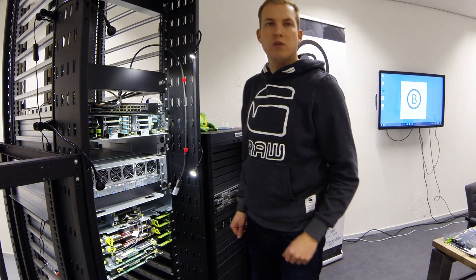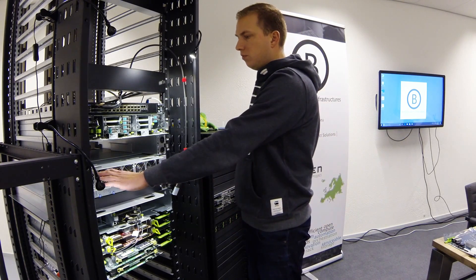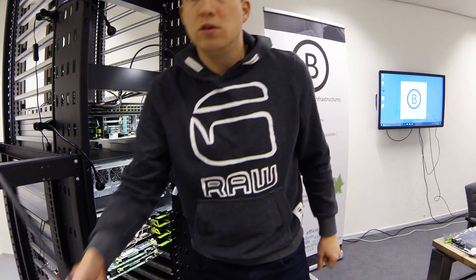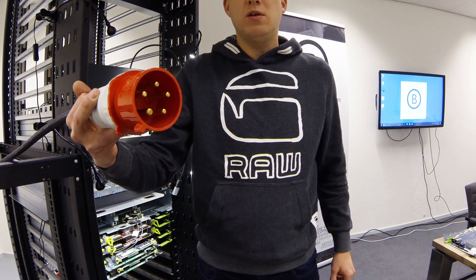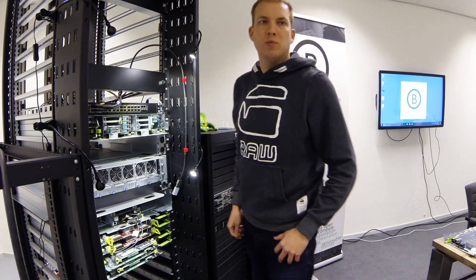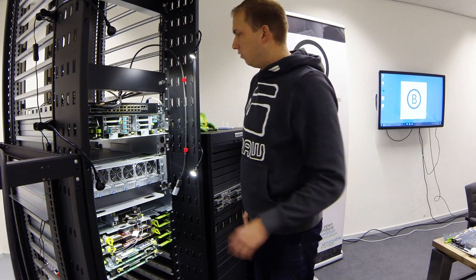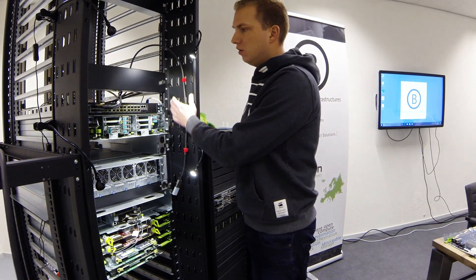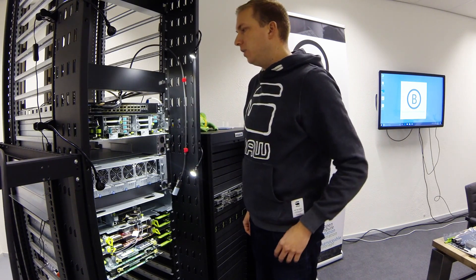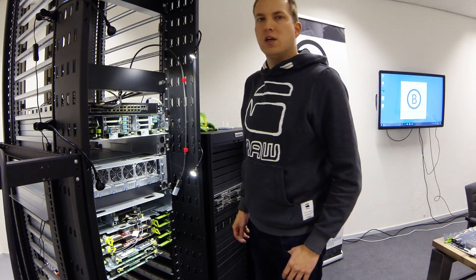This rack is based on the Open Compute open rack design. It has six power supplies in a 5 plus 1 configuration with dual three-phase feed. It has three busbars and an option for a management card. As you can see, all the cabling is done at the front of the rack in this cabling zone. It's built earthquake proof and can be shipped with all the gear inside.